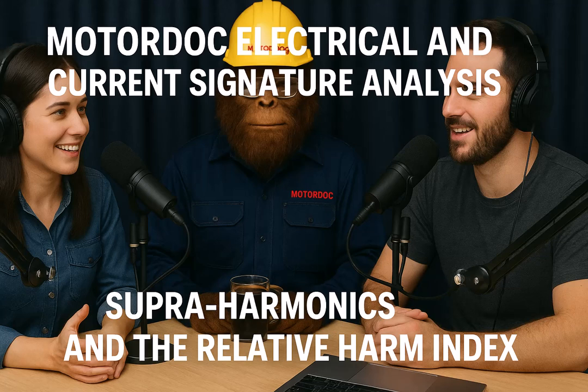And where did these ideas come from? What's the history here? Well, MCSA really emerged back in the 80s. The initial focus was on testing electric motor rotors, assessing their condition. Okay. ESA, which sometimes got called MCSA in the early days too, confusingly, was developed around the same time by Oak Ridge National Labs. Ah, Oak Ridge? Yeah. Their scope was wider from the start, looking at bearings, gears, other electrical bits, mechanical bits, especially in things like motor-operated valves. And I remember reading early on, people thought these methods could directly spot winding shorts. Is that right? That's right.